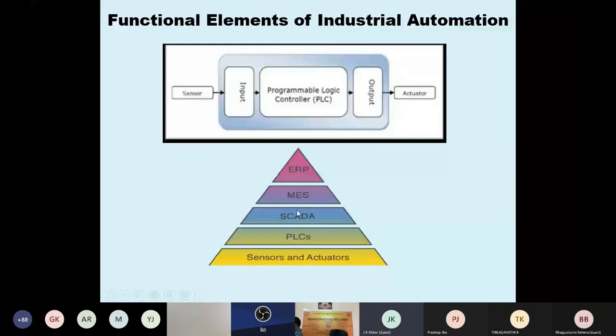If I go in a pyramidal structure, the sensors and actuators are the field instruments. Then the signal goes to the PLCs in a control room, and then the SCADA system, supervisory control and data acquisition system. Through the SCADA system, the operator or engineer can talk with the machine, and can stop or run the machine from the control room. Then the management information system means everything is connected to the internet, so management can get all information. Also any stockholder or shareholder can monitor our activities day to day, or shift-wise profit or loss, or any damage or any process happening inside our plant. They can visualize it now because of the industrial Internet of Things.